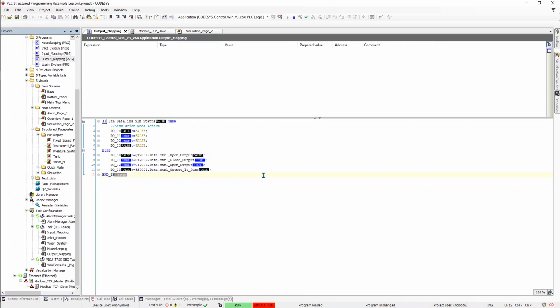There's still a simulation element to it, but the simulation element is just to make sure things are safe if we're running in simulation mode, because there may be times where you have a sort of pre-commissioning run through and assets and stuff are actually connected to your PLC, where you don't actually want to pass any outputs to start a pump. That panel might be powered, the pump might be powered. We don't actually want to start anything because we're still running in simulation. This just ensures that that can't happen, and make sure that you don't run things alongside simulation.